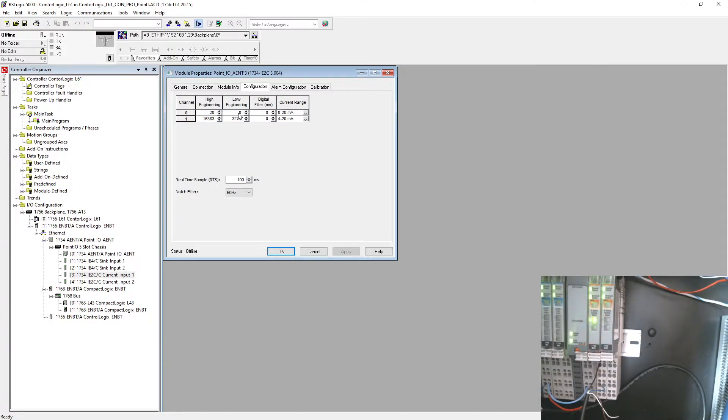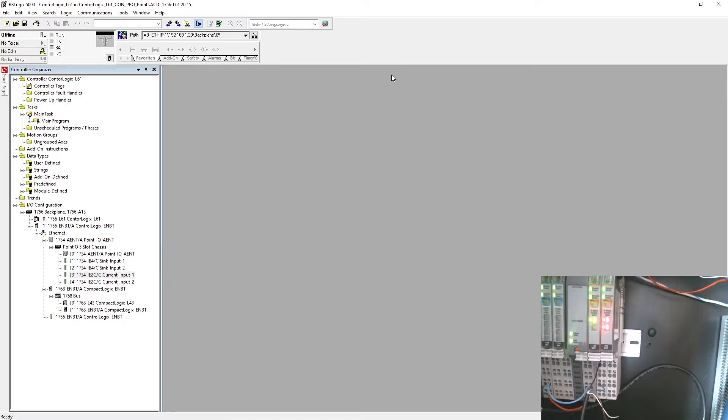In property, what I did on the high engineering side and configuration side, as highest I put 20 and lowest I put zero. On the alarm side, I put high-high when my current value will go above 18, my high alarm when it goes above 16, my low alarm will trigger when it's under 4, and low-low when it's under 2.